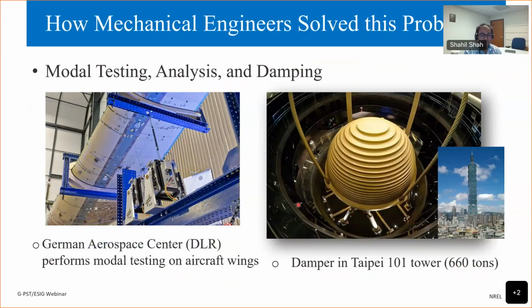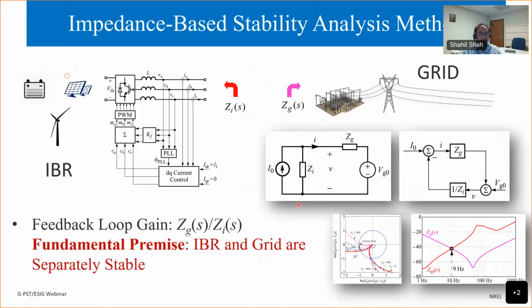So has this problem been solved elsewhere? Yes, mechanical engineers solve this problem every day. They have a similar issue. The mechanical structures are complex, with complex geometry and material properties, which are hard to model by equation-based models. And they have to rely either on measurements or on finite element simulations. So the solution that they have developed is modal analysis tools, where you excite the structure at different frequencies by some vibration mechanism and then measure the response at different points. We use this data to understand what the oscillation modes in the system are, what the damping of different modes is, what part of the structure is participating in what mode, and how to design a damping solution. That has been done by mechanical engineers. And we have a similar method in power systems, which is impedance-based stability analysis, which is what I'm going to talk about today.